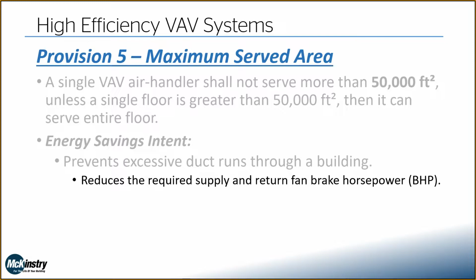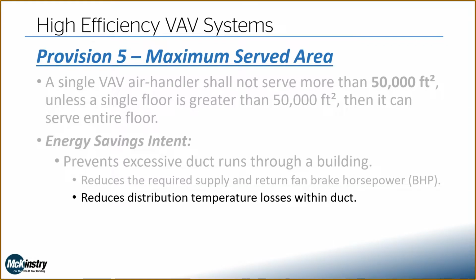It reduces the required supply and return fan brake horsepower, so we can downsize our fans at the air handler to serve that space. And it reduces the distribution temperature losses within the duct. So if we're sending cool air down that duct, the further it has to go, the more distribution losses you're going to have on its way there.